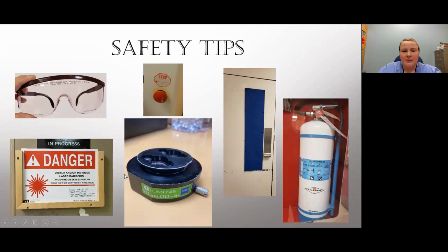At the bottom here is what I was talking about for the microscope safety lens. This one's by Lumenis. It's for a Zeiss microscope. Again, 532. It has an OD of 6+. So this goes in the microscope and protects anybody looking down the microscope, so the doctor, for instance, is protected without having to wear glasses while looking through it. On the right of that is a window covering. So this would be specific to wavelength and OD as well, optical density. This one here is kind of a snap-on version for the window inside the door. And on the right of that is a fire extinguisher.